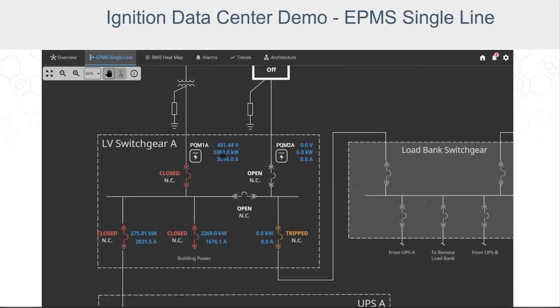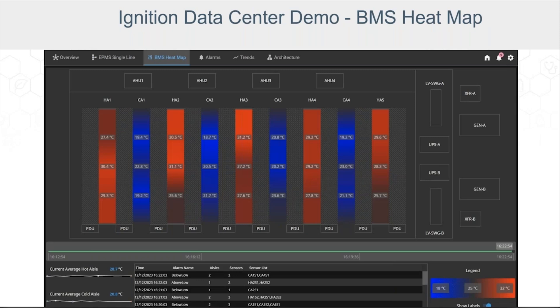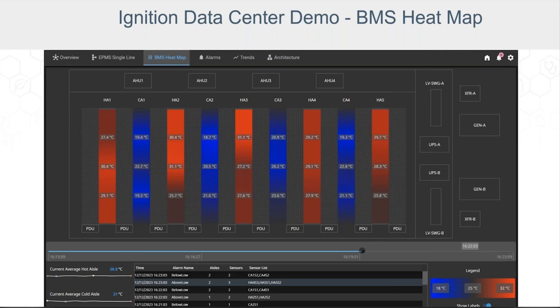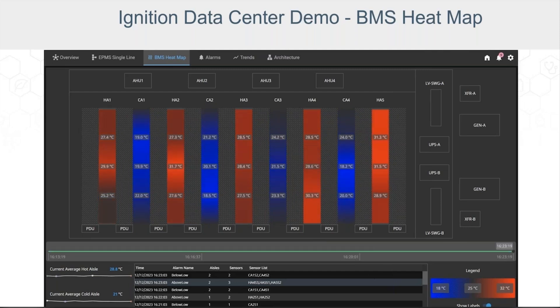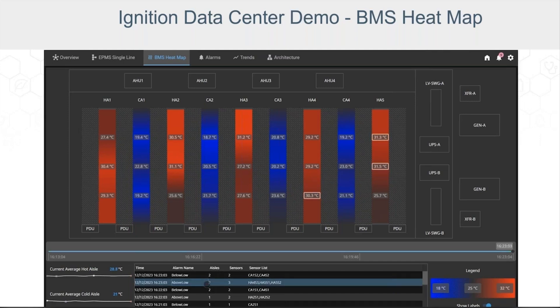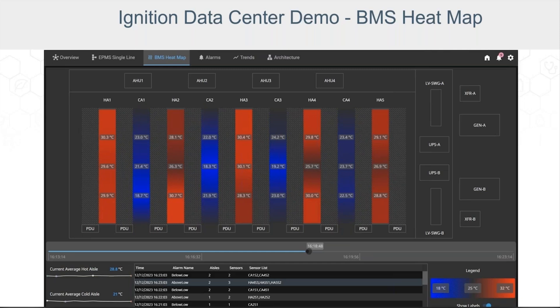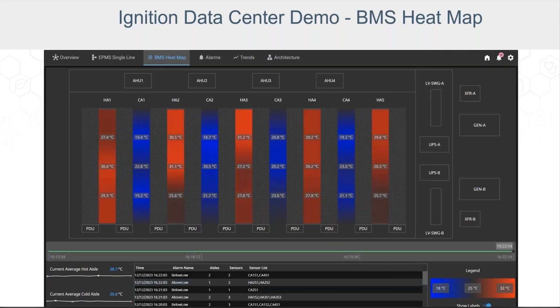Next, let's step over to the BMS heat map. Here we have a heat map showing temperature status for the hot and cold aisles in this section of the data hall — it's typical of what you might find in a building management system. When the time select bar below the aisles is green, the aisles and temperature sensors are depicting real-time values. A neat feature we've added is the ability to play back historical data — selecting an alarm from the table at the bottom will show the aisles and their temperature values at the time the selected alarm occurred. The time select bar changes from green to blue to indicate historical values, and temperature sensors in alarm highlight with a white border. You can also simply drag the time select bar to any time of interest to see historical values.